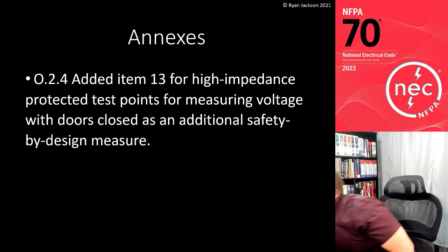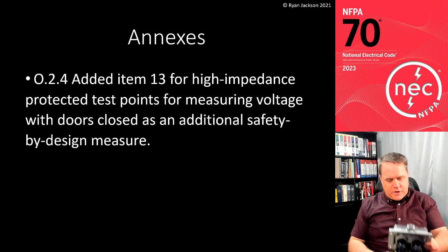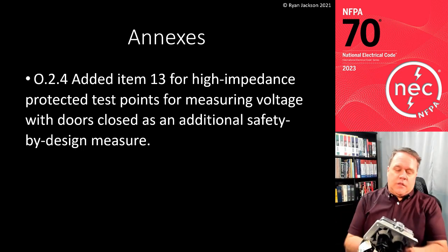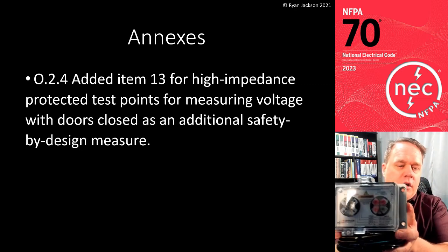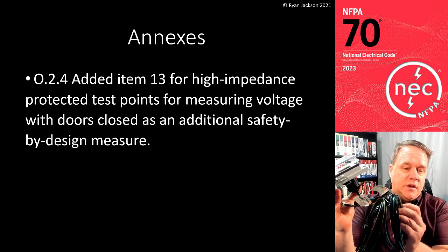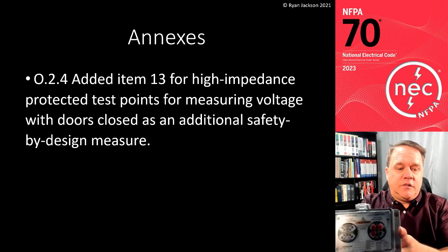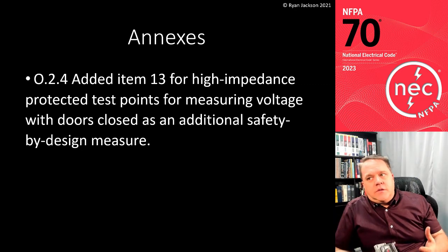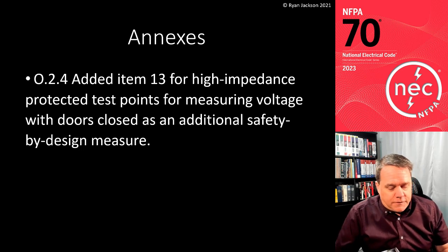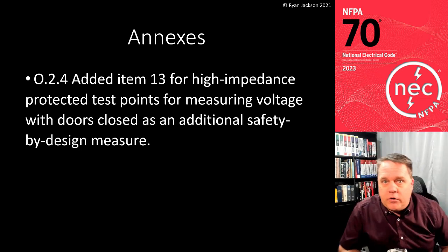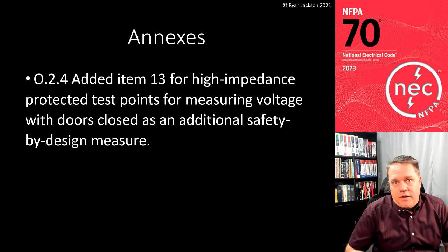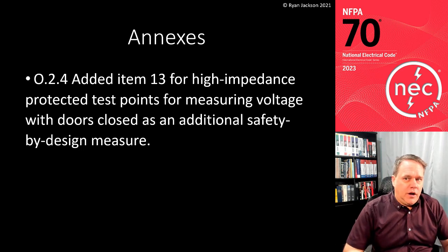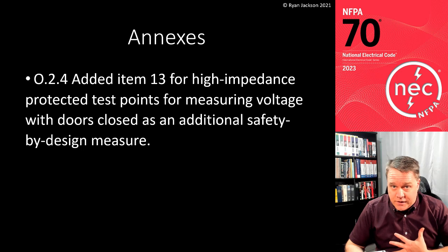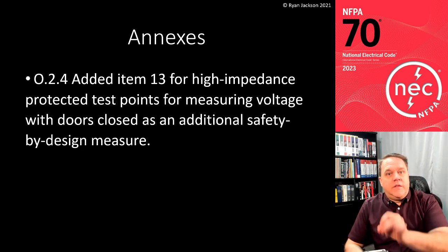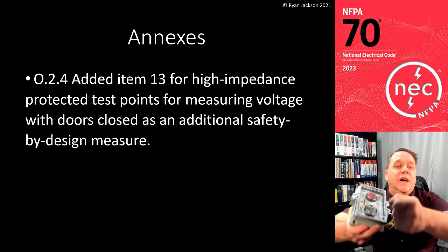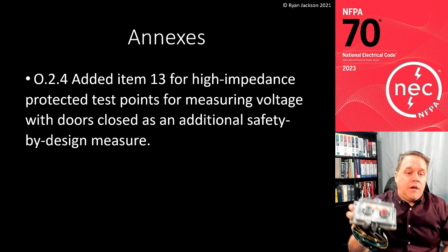All right, so let me grab my sample here that my friends with Grace Technologies were nice enough to send me. This is something that can be installed on the front of a switchboard or switch gear, and you can see it's got the wires that connect onto the equipment, and this is basically a test point. So if you've got high incident energies especially, so if you're working at a facility where this equipment has 30 calories of incident energy or 50 or 100 calories of incident energy, yeah, even if you dress appropriately for it, I don't want to be in a piece of equipment like that, right? So what if I could test for the absence of voltage without opening the doors and getting my hands and my meter inside the equipment? What if I could use a test point like this?